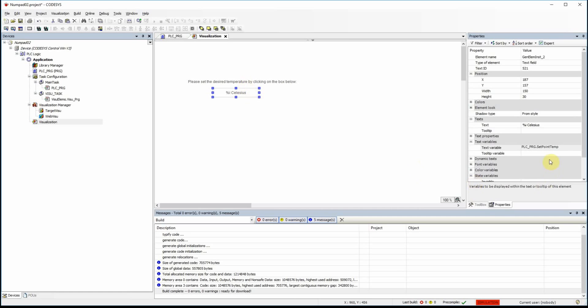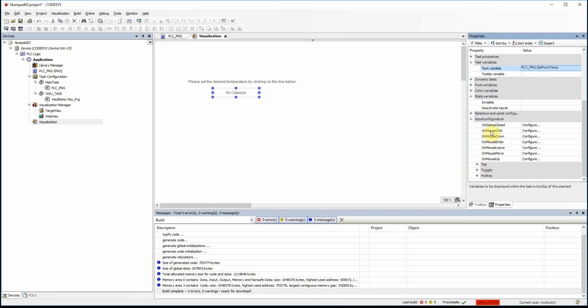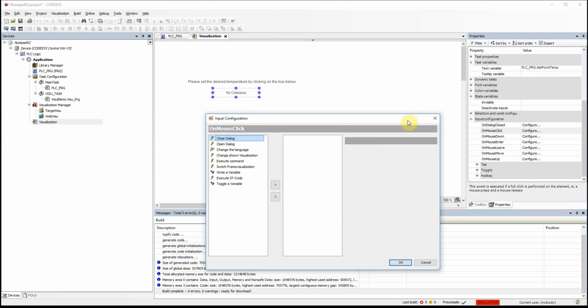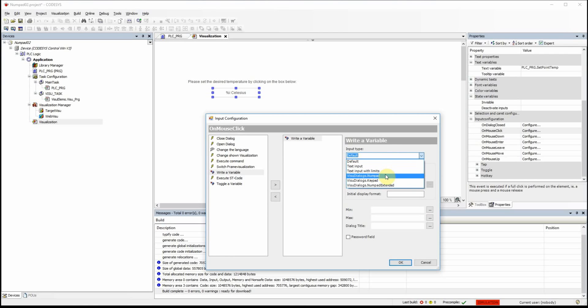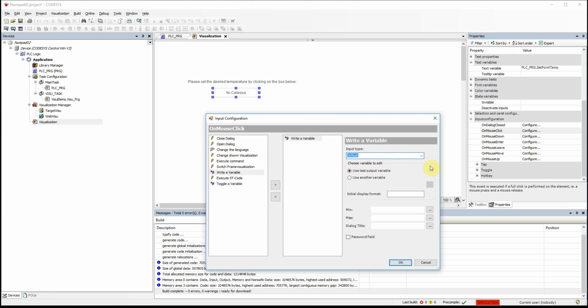If we select this element and go to the input configuration and click on 'On Mouse Click,' one way is to choose the 'Write Variable' option and add it to this element. Here we can determine the input type. We have these options: default text input, text input with limits, numpad, keypad, and numpad extended. Choosing 'Write Variable,' we can write to the output variable of the text field — the desired temperature. We can set a minimum value, a maximum value, a dialog title, and we also have the option of using a password field.